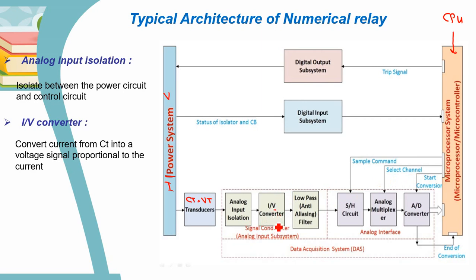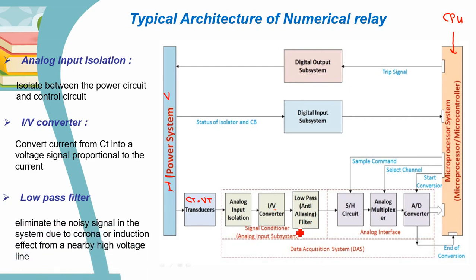Then we have the low-pass filter, also called the anti-aliasing filter. This filter is used to eliminate noisy high-frequency signals that occur in the main signal due to corona or induction effect from a nearby high-voltage line. It passes low-frequency signals such as our power signal at 50 or 60 Hz, and eliminates the high-frequency noise.